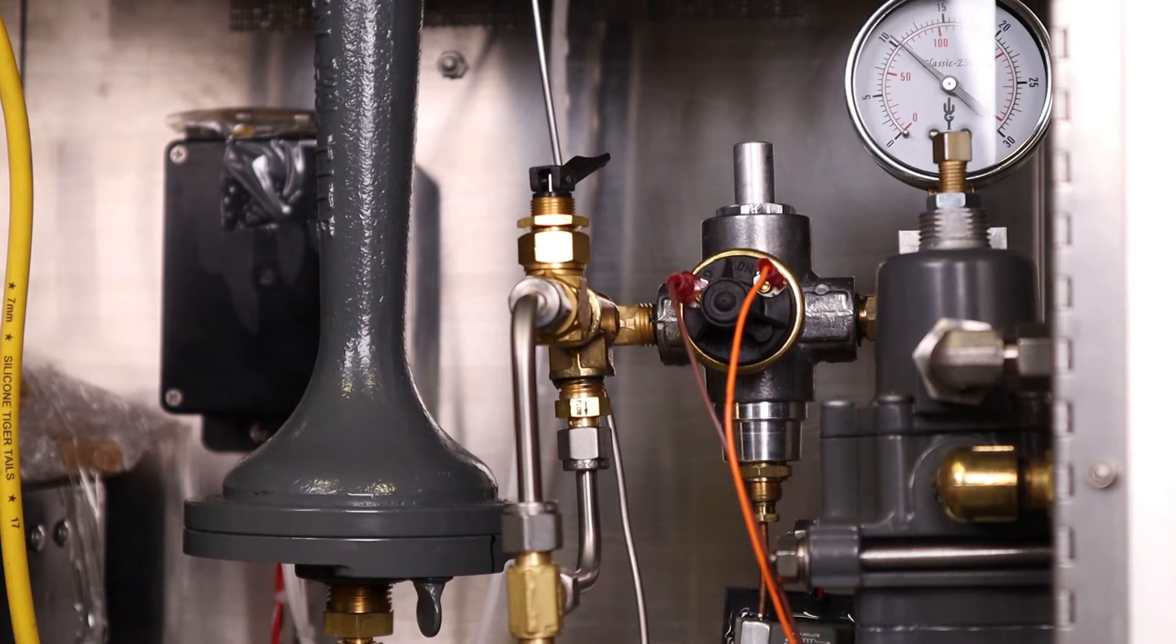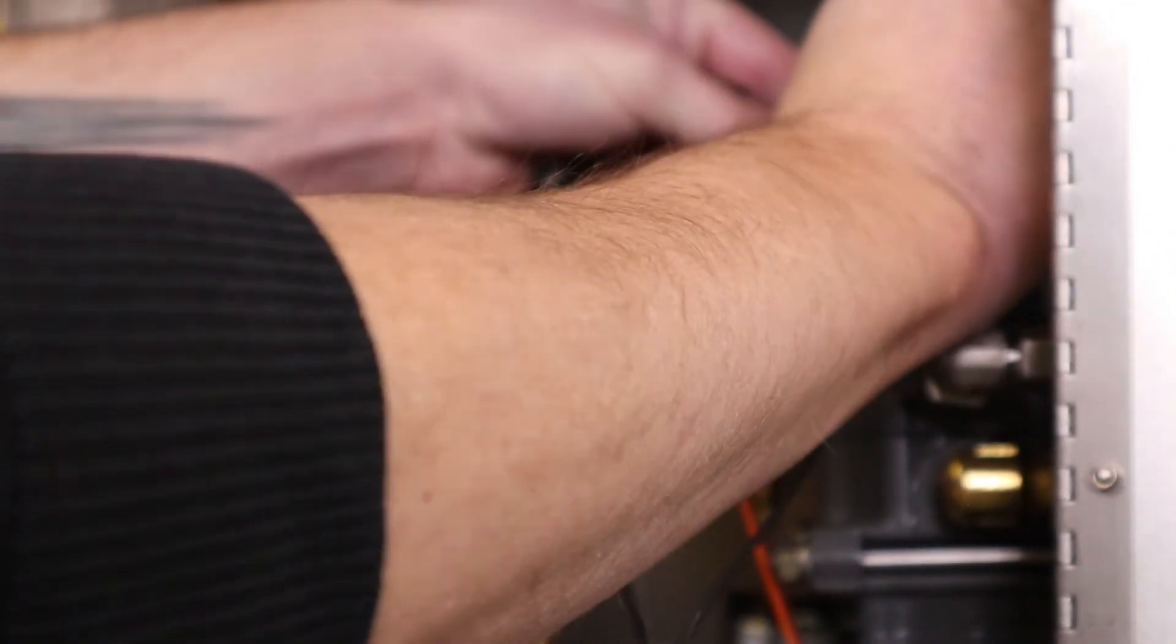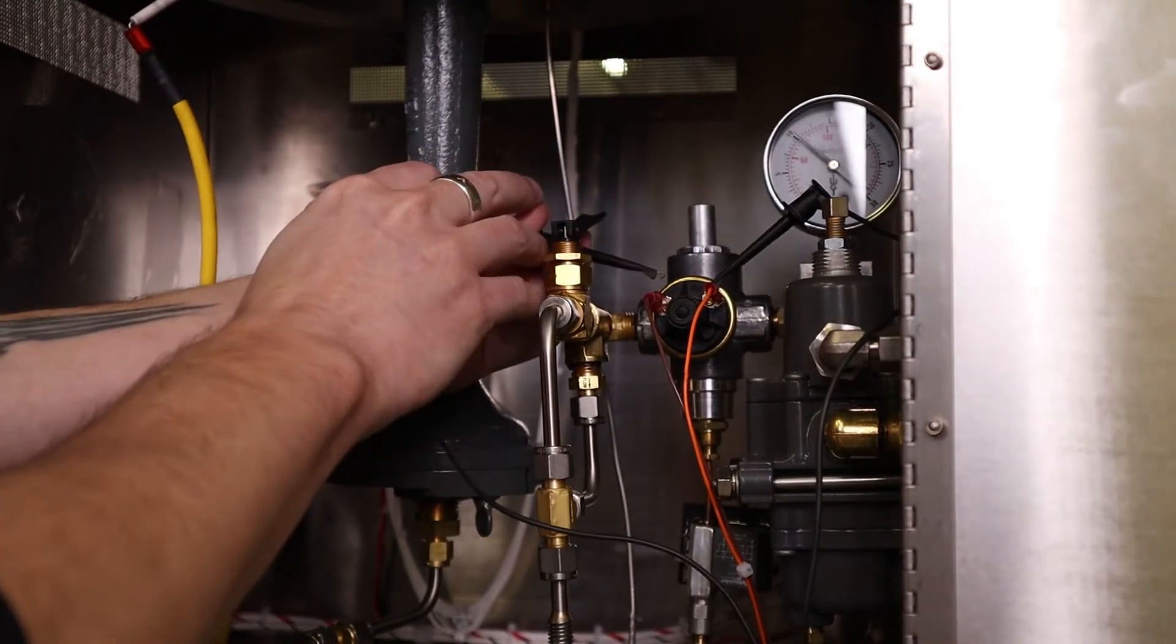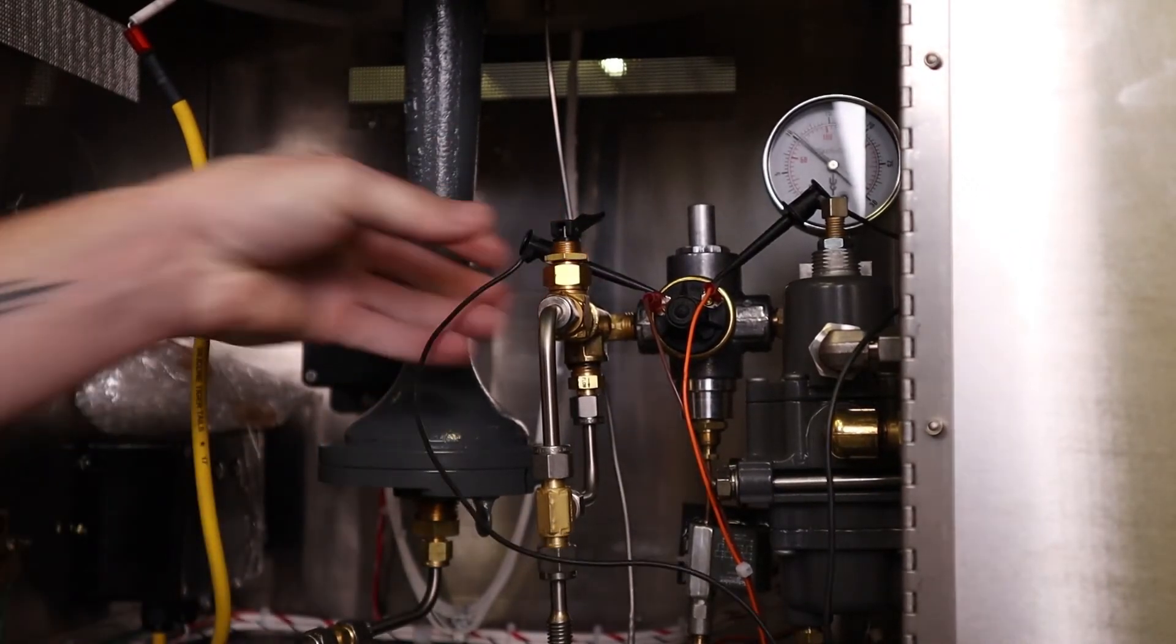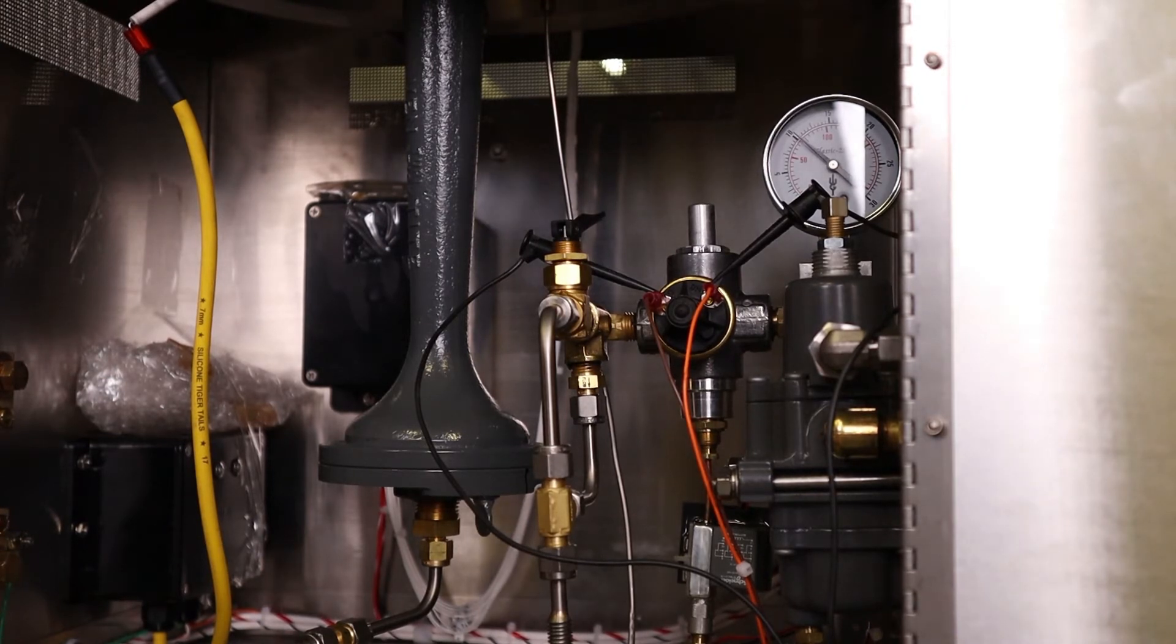Next, we'll check the operation of the ignition system by shorting the terminals of the pressure switch. I'm going to take this jumper and put a clip on either side. At this point, you should hear the ignition sequence start to tick. It should be loud and strong.